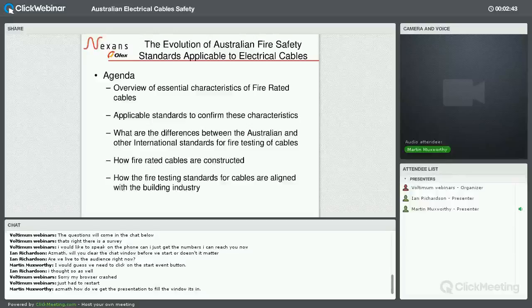The word fire-rated cable gets used quite a bit in the industry. It's reasonably well known, but it's still worth recapping on the essential characteristics of what a fire-rated cable actually is. And then what I'll do is I'll look at the standards that are applicable to confirm the characteristics of fire-rated cables.